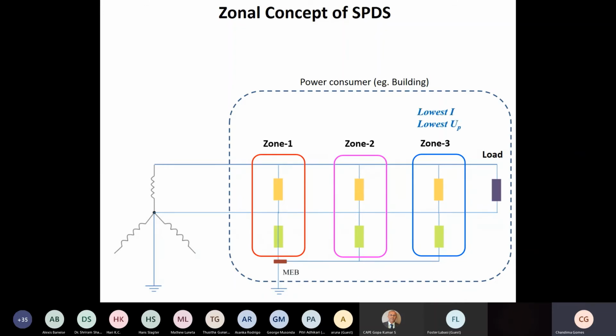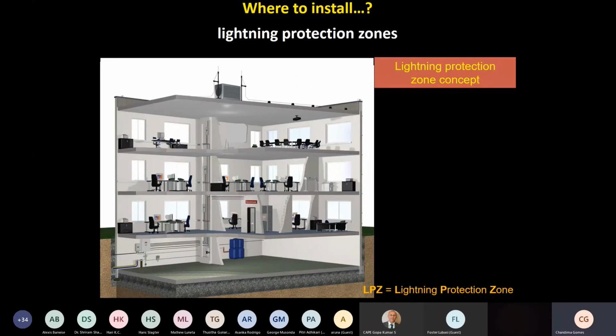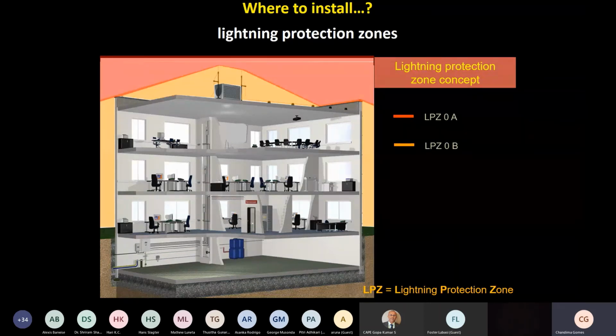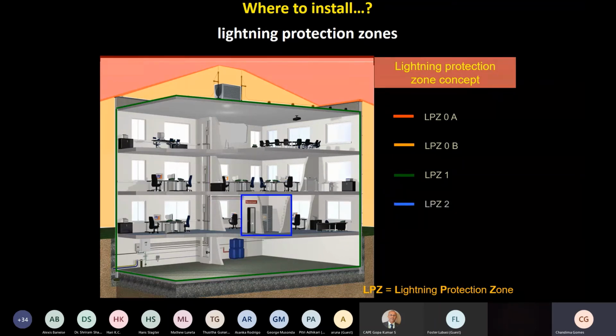And zone 3 will get the lowest I and lowest UP, and zone 1 should have the highest I and highest UP, and zone 2 is in between that. So, the lightning protection zonal concept, if I put the same thing I discussed with you into a diagrammatic form, this is what we get. We call zone 0A what is not protected by even your structural protection system. Then zone 0B what is protected by your structural protection system. Then LPZ1 is the place where you just enter into the building. Z2 and Z3, the same thing in a different way, in a pictorial way.